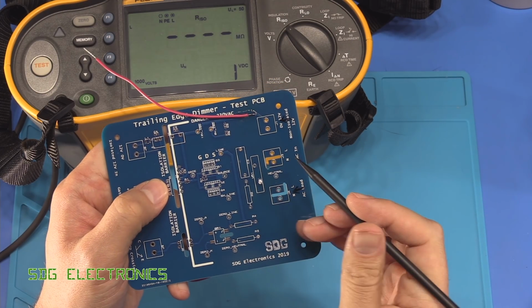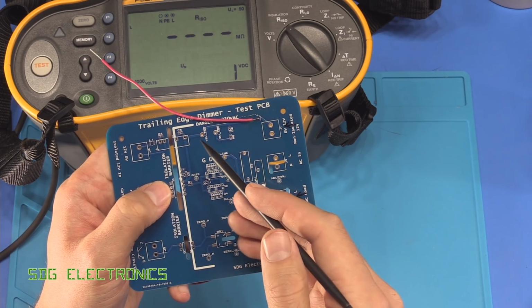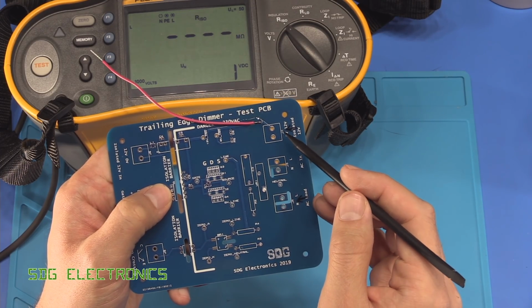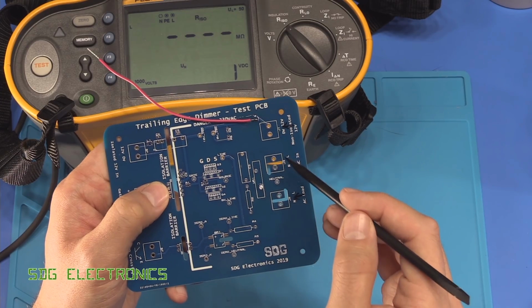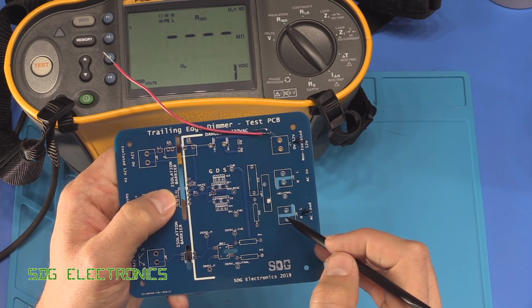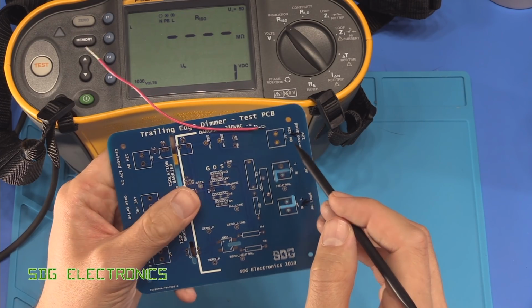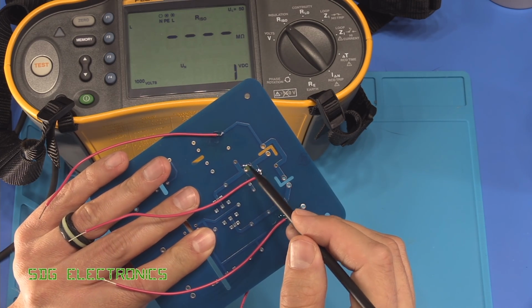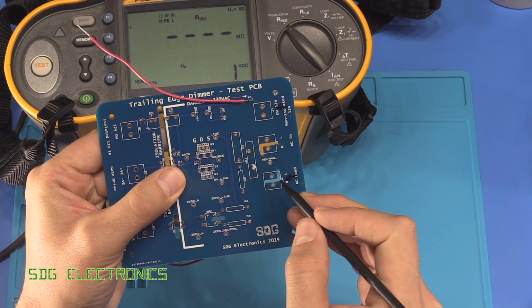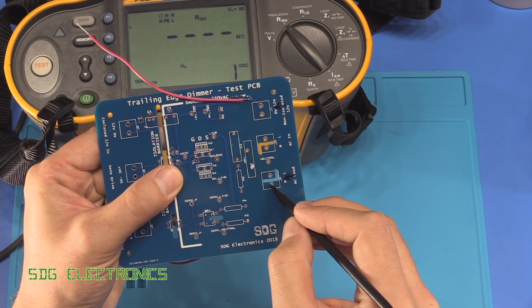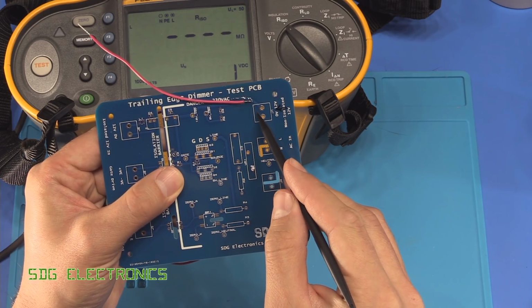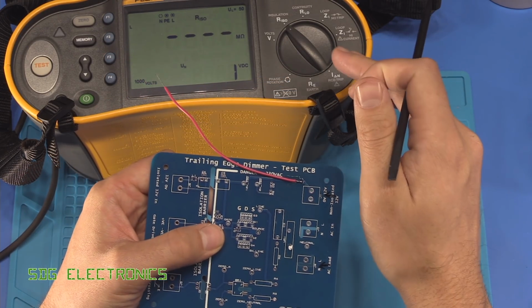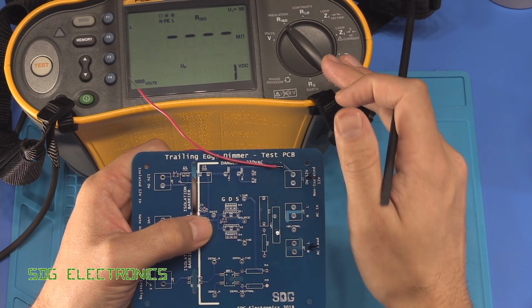Right, so what we've got here is one of the PCBs that are used for designing the trailing edge dimmer, and we've got on the right hand side some terminal blocks, and you can see some of them have slots in them and some don't. So what I've done is I've cut the traces where applicable and then attached some wires to this terminal block here that has the slot and this one that doesn't. I thought what we'd do is just have a look at the difference in insulation resistance.